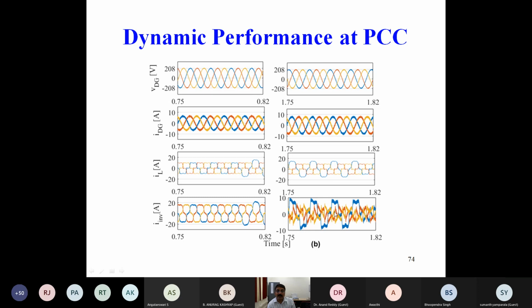Here you can see the inverter current is disturbed. Why is it disturbed? Because the load current, one phase, has a disturbed current, that means unbalance of current is introduced. But the DG has supplied the current in a balanced manner, voltage and current, it is not unbalanced. Although the inverter is having unbalanced current because the load has unbalanced current, the DG is supplying constant current.